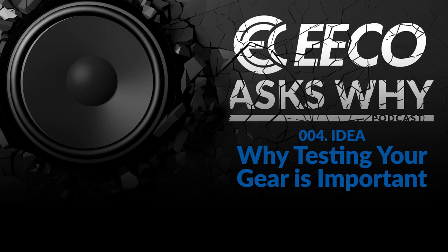But when we start talking about a short circuit and coordination study, that's really about making sure that all of your breakers or fuses within your electrical system, which all feed each other, that's what a system does. You'll have a higher end part of your distribution system that feeds downstream equipment, and that might even feed downstream equipment from there. You want to make sure that if a fault occurs anywhere within that system, whether it be at the main incoming service switchgear or switchboards, panel board, or all the way downstream at the load, that the breakers or fuses, let's just talk breakers for the sake of this, are going to trip appropriately.